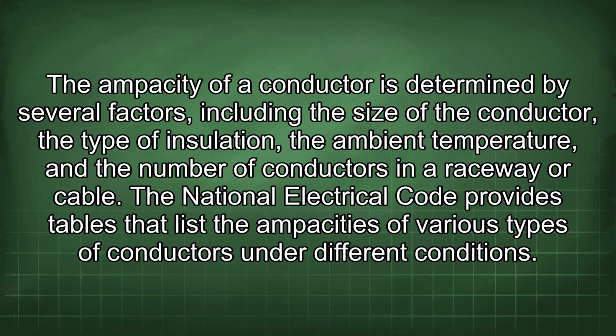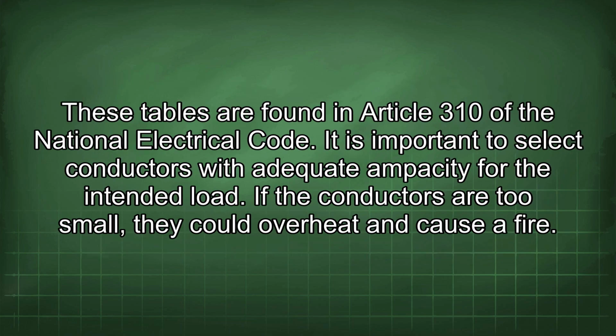The National Electrical Code provides tables that list the ampacities of various types of conductors under different conditions. These tables are found in Article 310 of the National Electrical Code. It is important to select conductors with adequate ampacity for the intended load. If the conductors are too small, they could overheat and cause a fire.